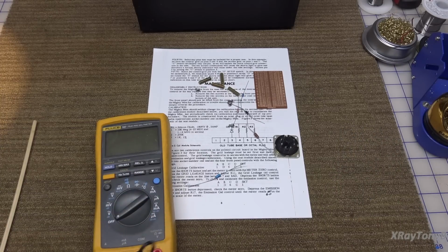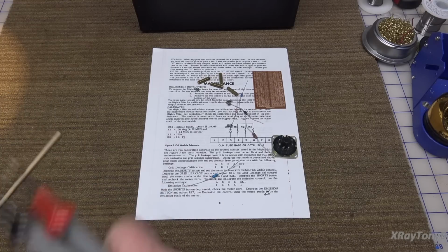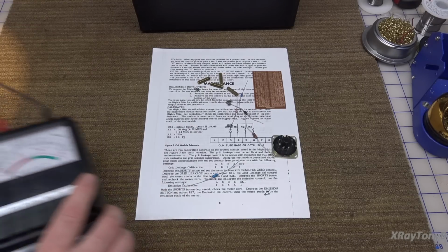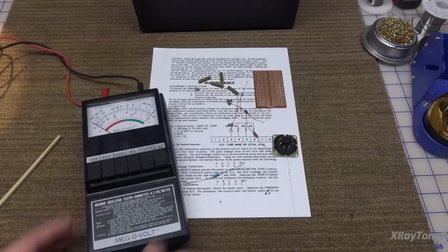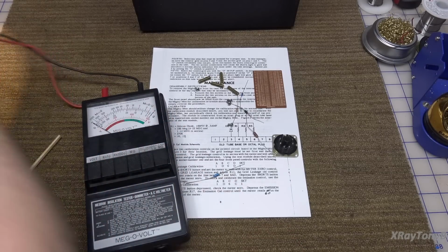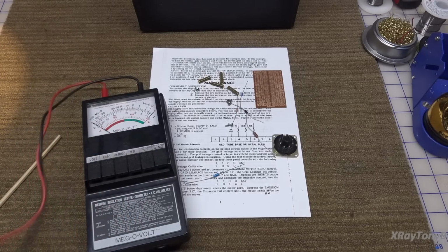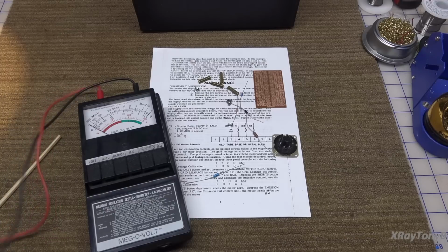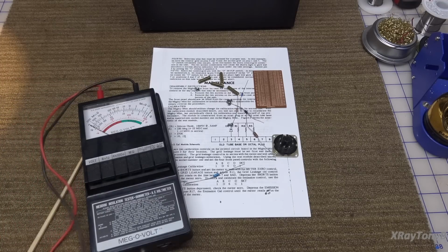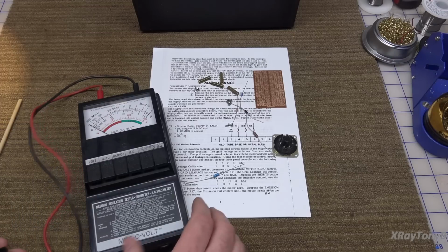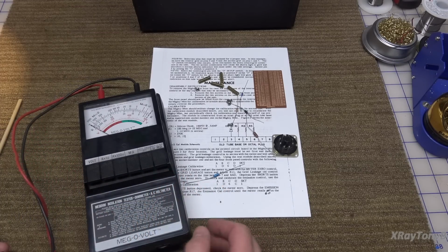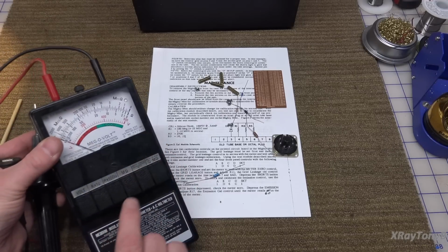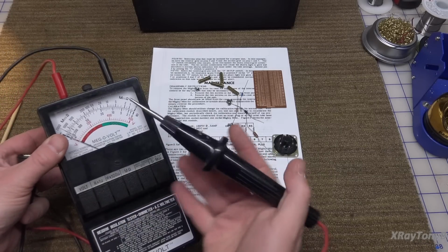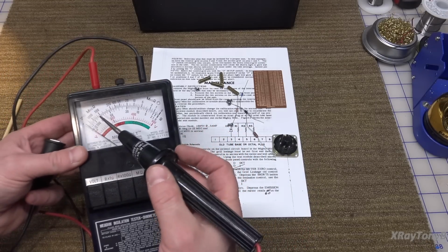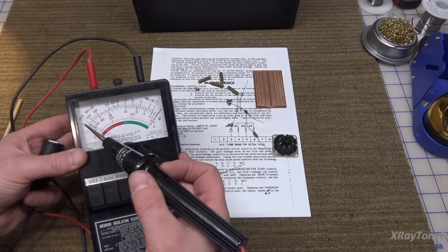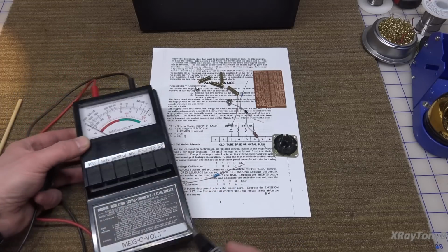Now, if you have to read really high resistances and your meter won't go that high, they do make a device specifically designed for high resistance, and it's called a megohmmeter, and sometimes they call them a megger. But essentially what these do is they work by applying a high voltage to the device. It's heavily current limited, and it allows you to measure really high resistances. As a matter of fact, you can see there is a megaohm range, and the lowest number it starts at is 1 megaohm, and it goes clear up to 500 meg, 1 gigaohm, 2 gigaohm. So it gets up pretty high.